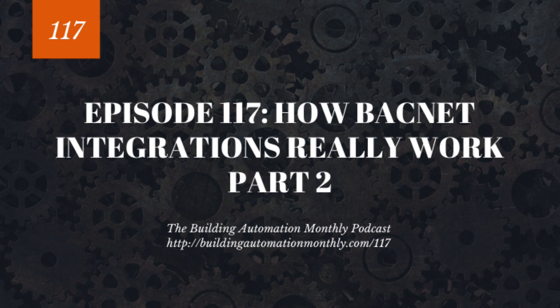And this is really important. This topic I'm going to spend a fair amount of time on in this episode because how you address your controllers is going to make a huge difference to the speed of your network, the ability to troubleshoot your network, the ability to organize your network. So some folks like to run their trunks with a supervisory device kind of in the middle and then have one BACnet MSTP trunk running off to the left and one running off to the right. I'm personally not a fan of that because it doesn't really position you well to take advantage of one of the most powerful things, which is a token.